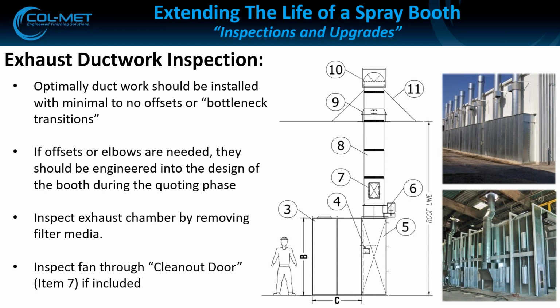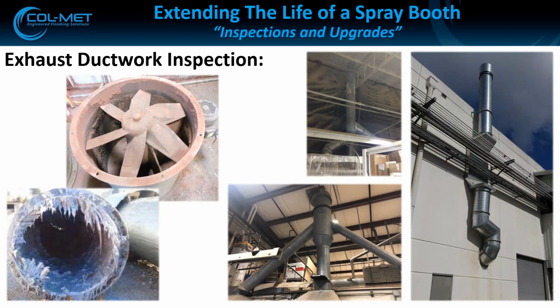Another way to inspect your chamber is when you're changing out your filter medium. Look in the filter chamber and see what it looks like in there. You can possibly look up through the stack and get an idea of whether our filtration is proper and whether it's been installed properly. To give you some visual examples of what I'm talking about, you see the picture to the left of a fan that's got some overspray on it.